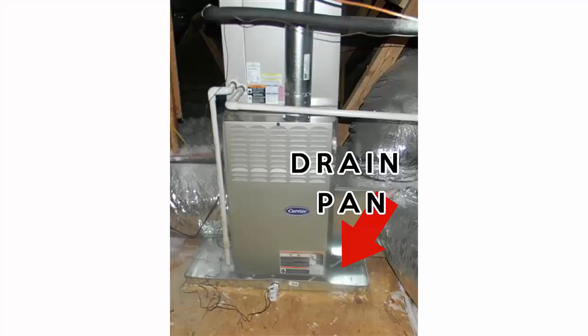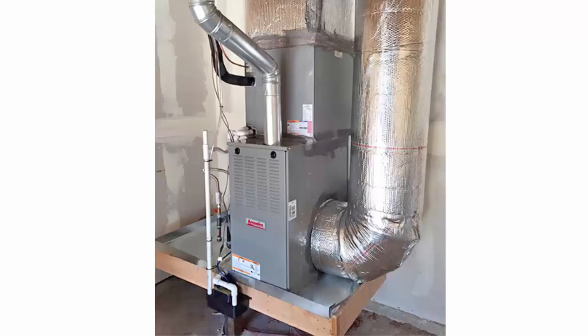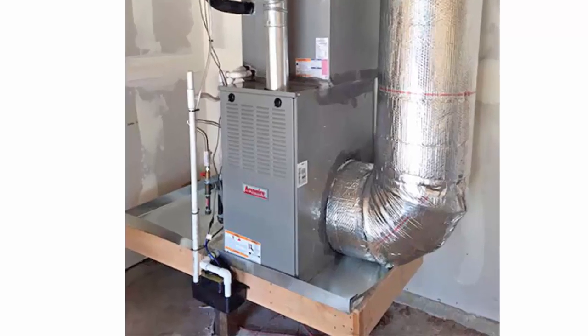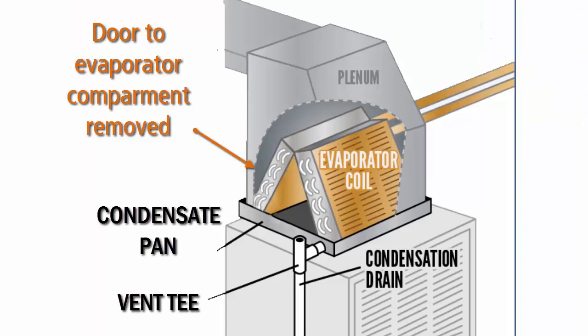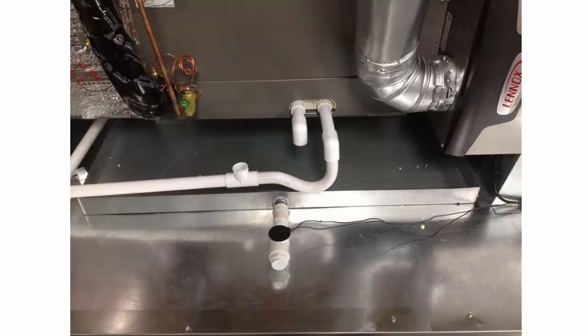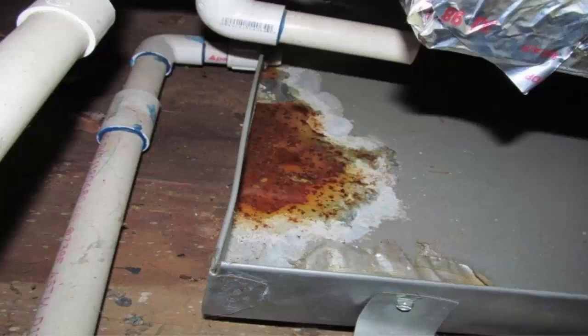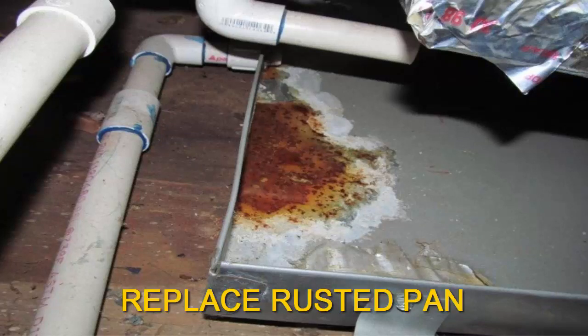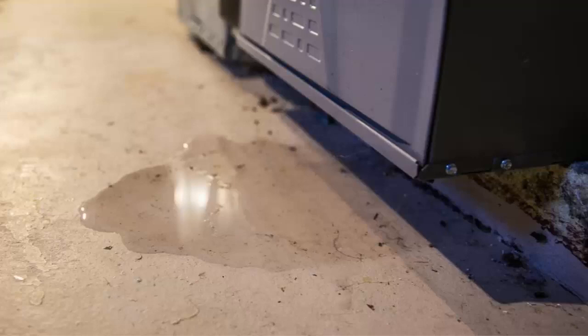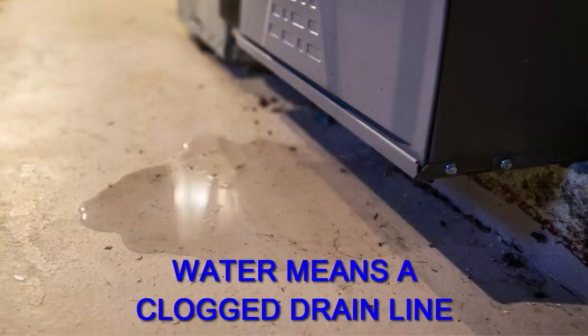Here's how. First, find the condensate pan. Usually this is a metal or hard plastic pan about 3 inches deep, sitting below the HVAC's air handling unit. In some cases, you may need to remove a metal panel to access it. The condensate pan should be nearly dry. If it has significant rust all over or is rusted out in sections, it must be replaced. Plus, signs of rust means there has been water backing up in the pan regularly, which is not a good sign. If the condensate pan has standing water in it, or if there is water on the floor nearby, there is a problem with the condensate drain lines.